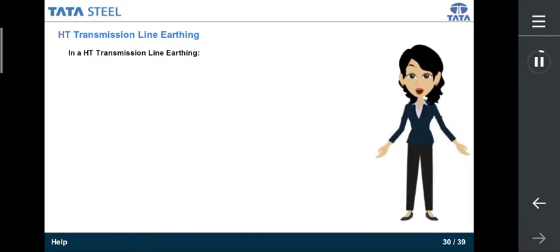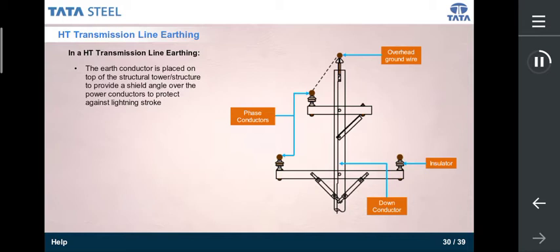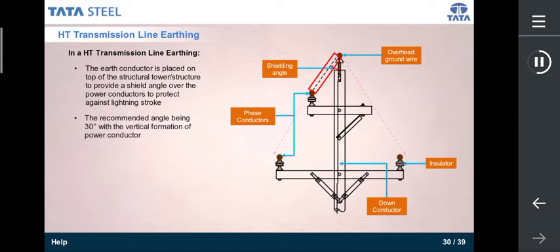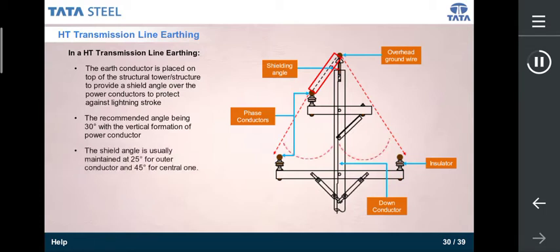Well, in this topic, we shall discuss earthing for high tension transmission lines. To understand this, you need to look at the figure given here. As you can see, the earth conductor is placed on top of the structural tower or structure to provide a shield angle over the power conductors to protect against lightning strokes. The recommended angle is 30° with the vertical formation of power conductor. This is also called the protection angle. The shield angle is usually maintained at 25° for the outer conductor and 45° for the central one. Let us move on to learn about the specifications for tower earthing.